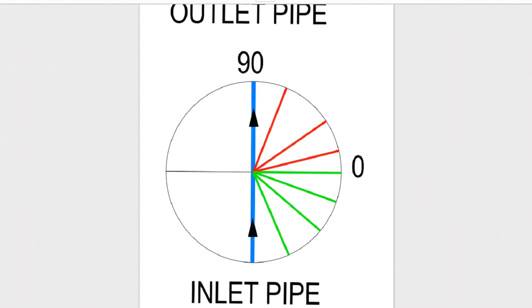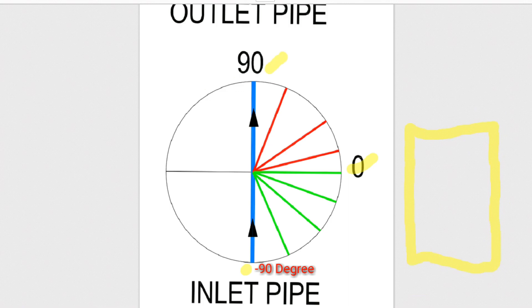Here is the answer. Looking at the inlet and outlet pipe directions: this is the manhole and this is the building. From the building to the manhole, I can provide the pipe connection at different angles — depending on toilet location — like this, or this, or this. So I defined 0 degrees, minus 90 degrees, and plus 90 degrees. Whatever angle is shown in green, between 0 degrees and minus 90 degrees, is acceptable for connecting to the manhole.